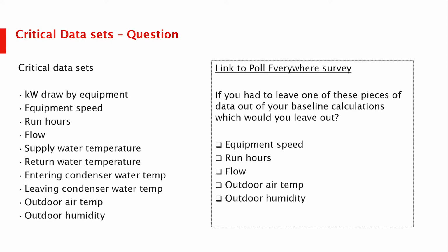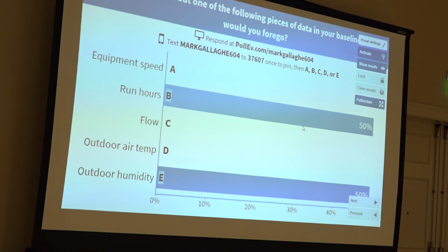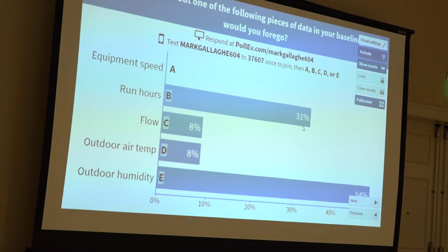Critical data sets we'd typically look for, if we could get everything: kilowatt draw, speed of all the equipment, run hours, flow, supply temperature, return temperature, entering condenser temperature, leaving tower temperature, outdoor air, and humidity. There would be more, but those we'd consider a base set of data we want. But if you had to leave one out, from speed, run hours, flow, temperature, or humidity, which would you be more inclined to leave out? It's a bit theoretical since we typically collect all of it, but it begs some further discussion.